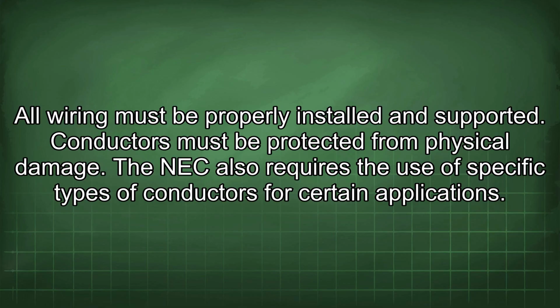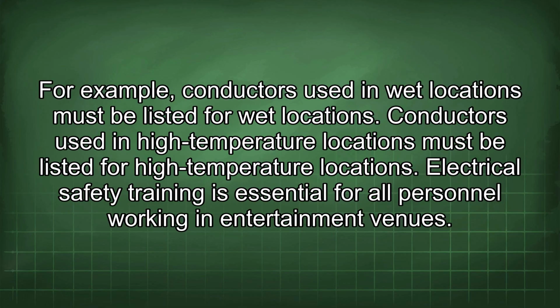The NEC also requires the use of specific types of conductors for certain applications. For example, conductors used in wet locations must be listed for wet locations. Conductors used in high-temperature locations must be listed for high-temperature locations.